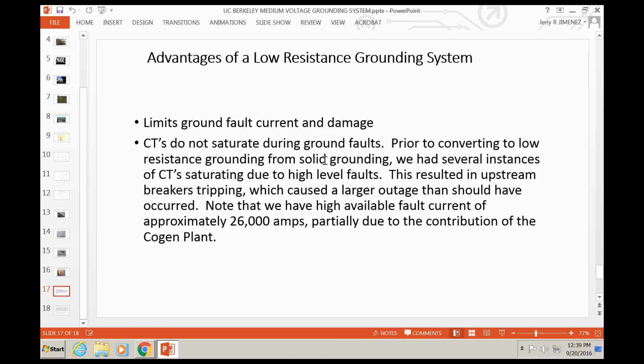Before we converted to the low resistance grounding, there were many instances of the CTs saturating due to high-level fault current. Even prior to having this low resistance grounded system, a single line-to-ground fault would result in full fault current, like I say, 26,000 amps. A lot of our CTs would just saturate, and we were getting a lot of miscoordination. We were getting upstream breakers tripping that shouldn't have tripped, and downstream breakers were not tripping. It was a little bit of a mystery till I really started looking into this and learned a lot about accuracy class ratings of CTs, the burdens on the CTs, and the types of relays we're using. So this has been a really, really good thing for us in preventing saturation of the CTs.